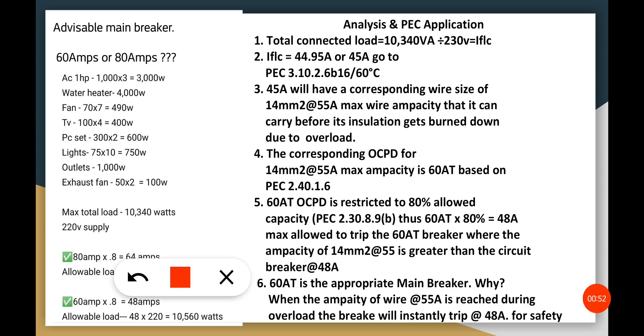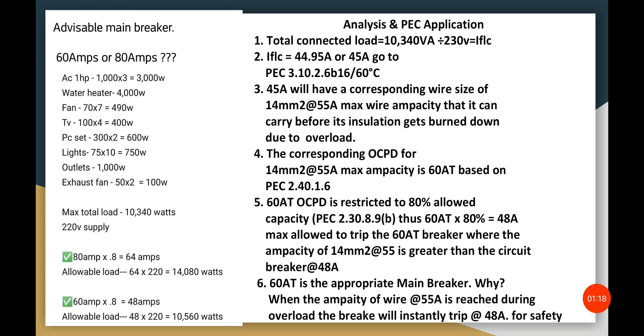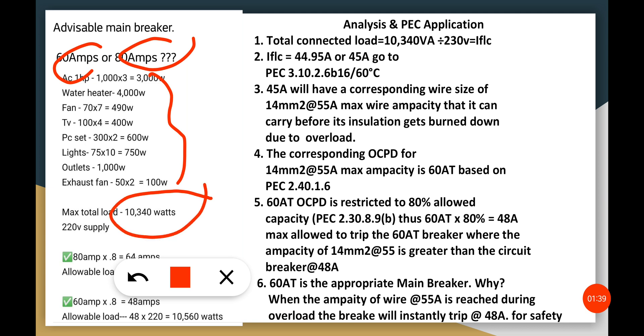We have a very interesting inquiry from a colleague of ours. He was asking: what is the advisable main breaker to be used from his load schedule — is it 60 amperes or is it 80 amperes? The load schedule came out to a total maximum connected load of 10,340 VA at a 220-volt single-phase supply. We are going to use 230 volts in our calculation.